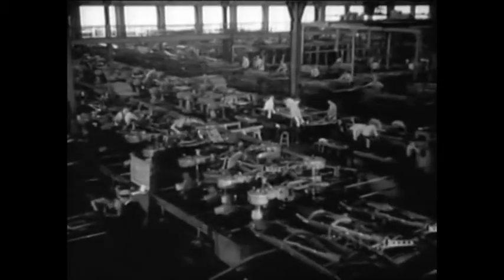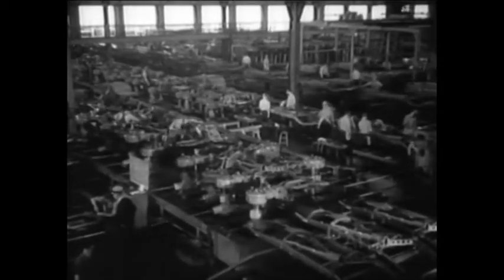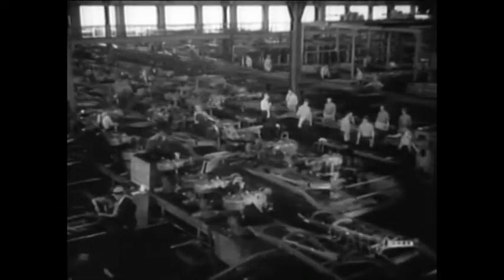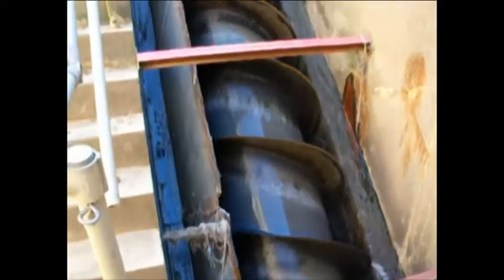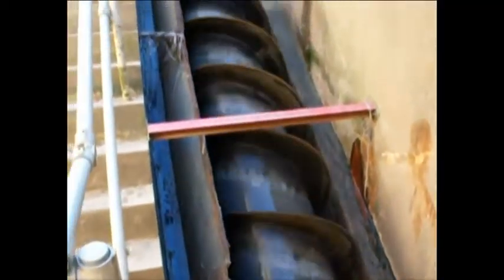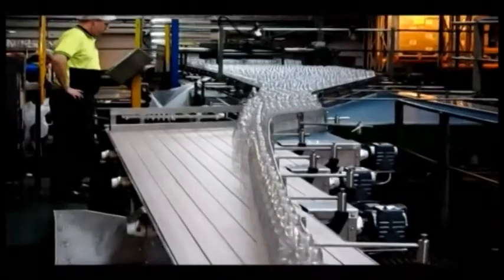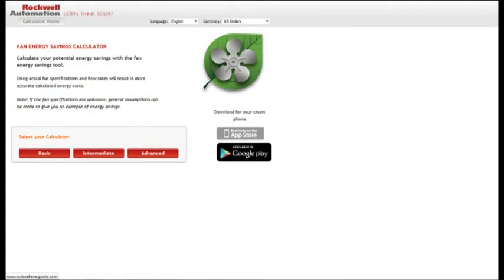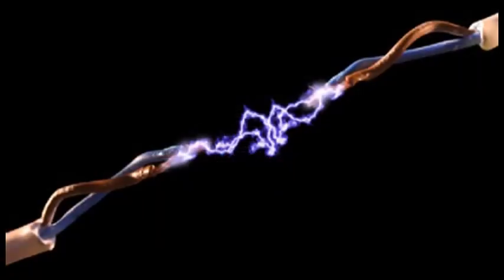the equipment they control. In the old days, you'd start your motor across the line with a combination starter. These are rugged devices that can easily withstand line disturbances. But modern facilities rely on the ability to vary the speed of their machinery to make production more efficient and more profitable. And mandates to become more energy efficient have put VFDs in control of more and more motors, placing them in jeopardy from line power issues.